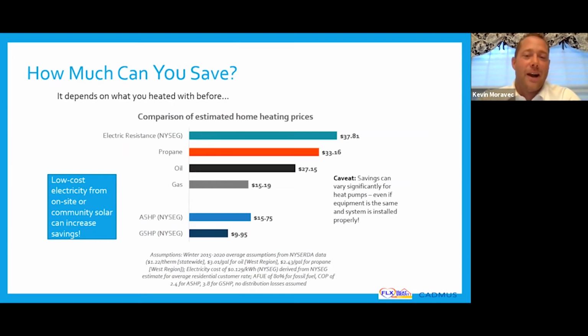How much can you save? Obviously this depends greatly from home to home, and even geothermal system to geothermal system. At the upper echelon of savings, there are variable capacity heat pumps with 12 different stages of operation, very similar to most air source heat pumps. The compressors can modulate based on demand in the home. What we mean by demand or load matching: the hotter it gets outside, the geothermal system just matches what the home needs to remain cool, and as it gets colder, the system ramps up just enough to keep the temperature set at 72.